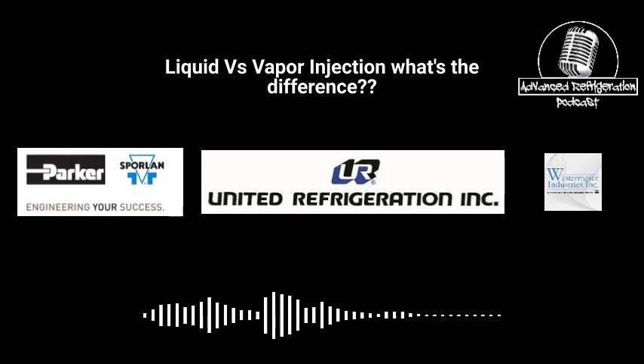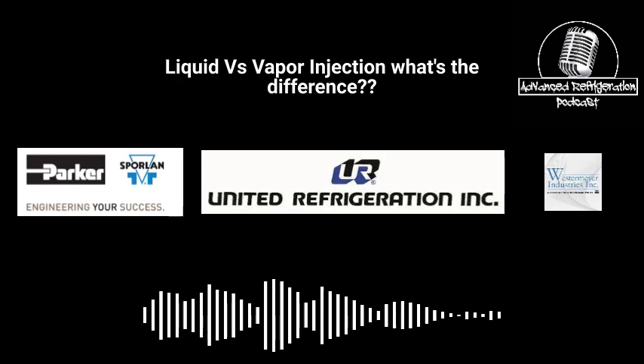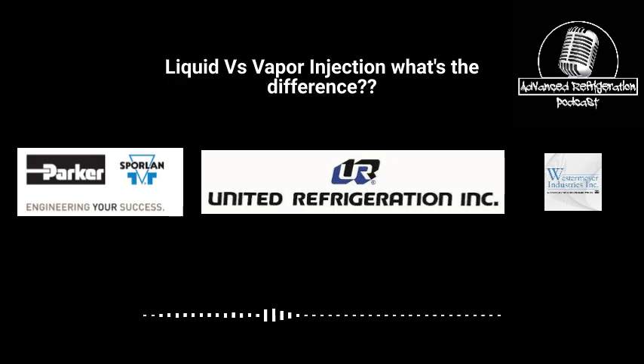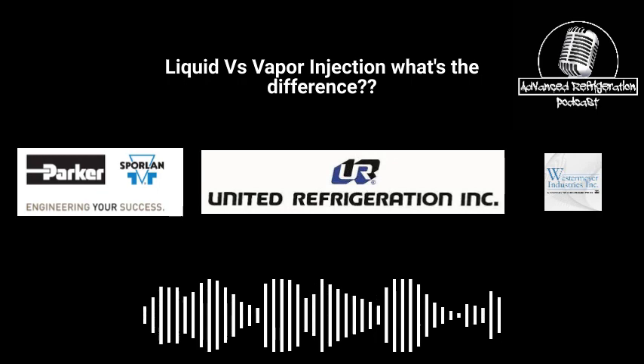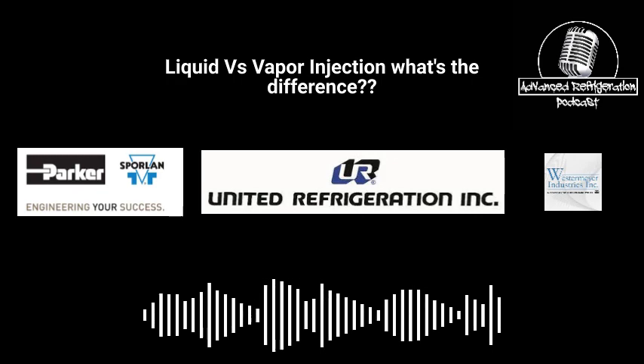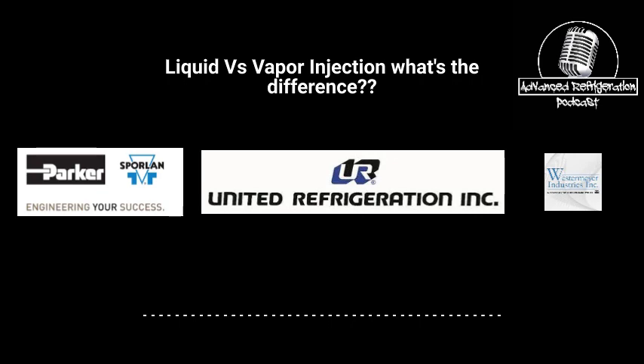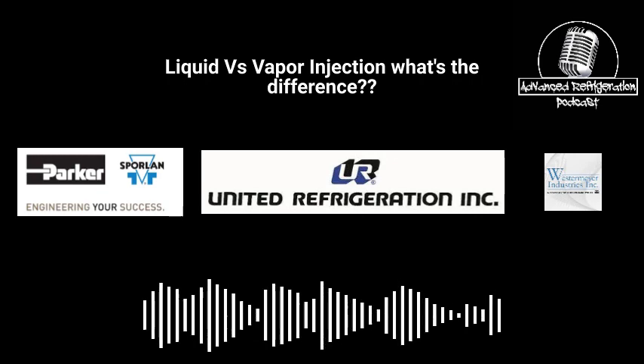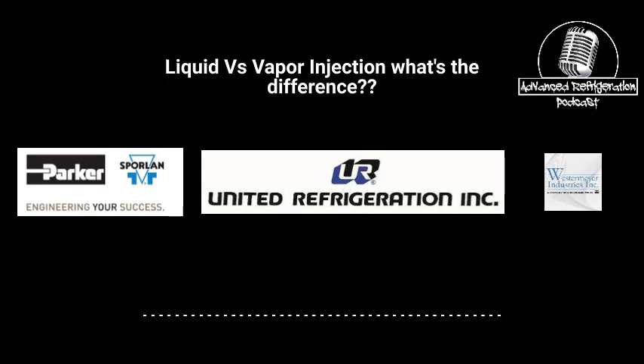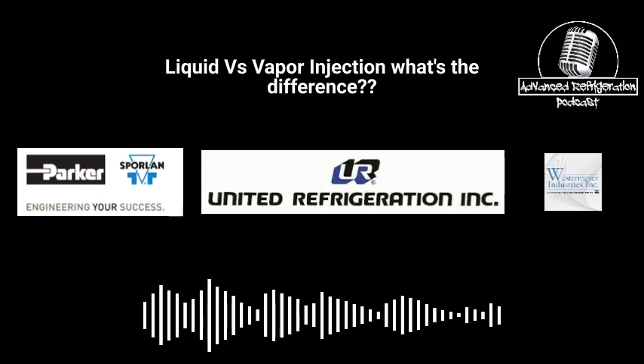I've seen that wreak havoc on racks, and guys having demand cooling issues or rack overheating issues, and it's post defrost, when for 10, 15 minutes the vapor coming back from that circuit that's coming off a defrost is 100, 200 degrees, and it's just overheating the suction and overheats that compressor. So I'm going to make a statement, because I've had people call me up on the phone saying, hey, my liquid injection line is flooding back. I've never had a liquid injection line flood back, because most of the time there's some sort of regulator. So if you have the option between your vapor injection and your liquid injection flooding back, not saying that it can't happen, but if you had 100 instances, it's usually going to be the vapor injection somehow flooding back because it's getting a bad superheat reading.